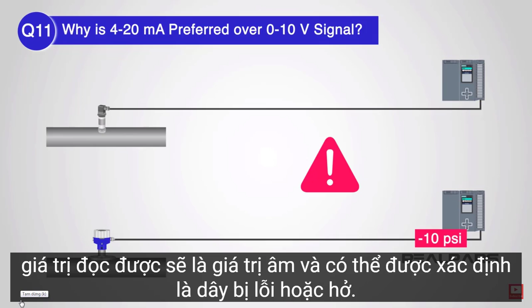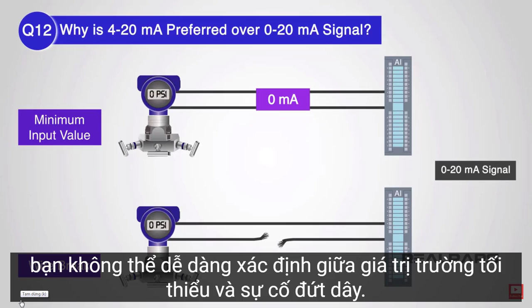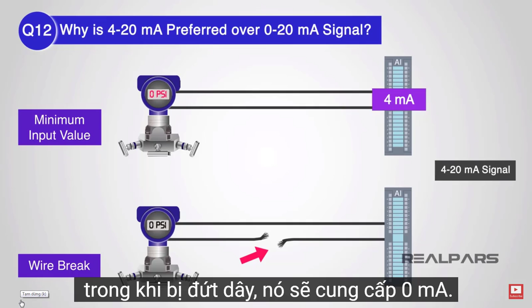Question 12: Why is 4 to 20 milliamp preferred over 0 to 20 milliamp? Answer: with 0 to 20 milliamp, you can't easily distinguish between a minimum field value and a wire break. With 4 to 20 milliamp, a wire break can be determined: at minimum input, the transmitter reads 4 milliamps, while a wire break reads 0 milliamps.